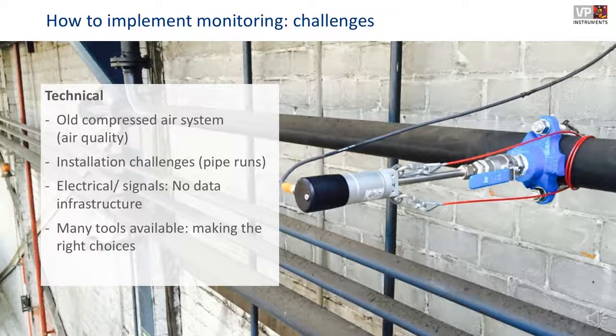On the electrical side, we aim for a direct connection to the company network to avoid long cables, because cables are expensive and carry a higher risk of errors. We've seen cables or Modbus signals being twisted, leading to hours of troubleshooting. When you can use Modbus TCP, all you need is an Ethernet plug, plug it in, and give the meter an IP address—making installation of a flow meter much easier.